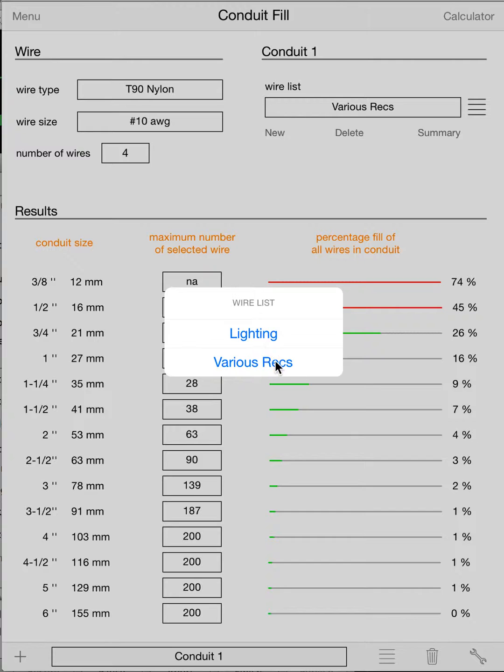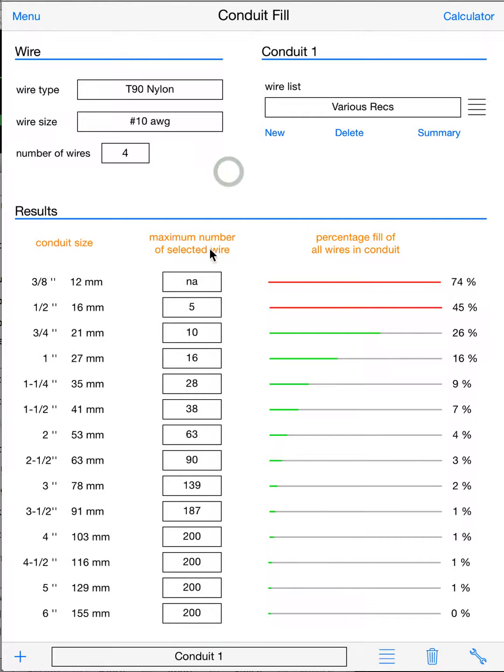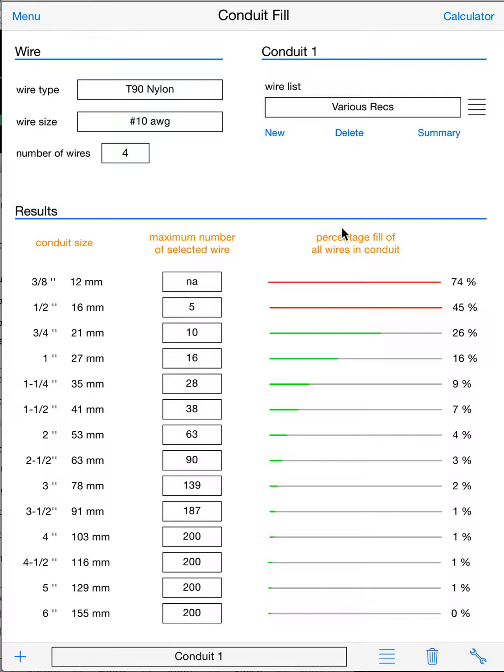Okay, so now we have a single pipe with two wire bundles: one lighting, one various recs. Now our maximum number of selected wire is not as important—it is showing the selected wire, so number 10 T90 your maxes—but now that we're doing a more complicated calculation, we're going to look at this column, which is percentage fill of all the wires in your conduit.